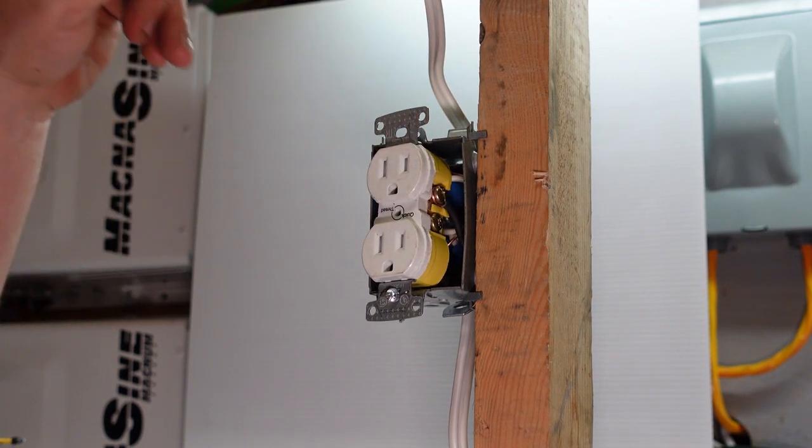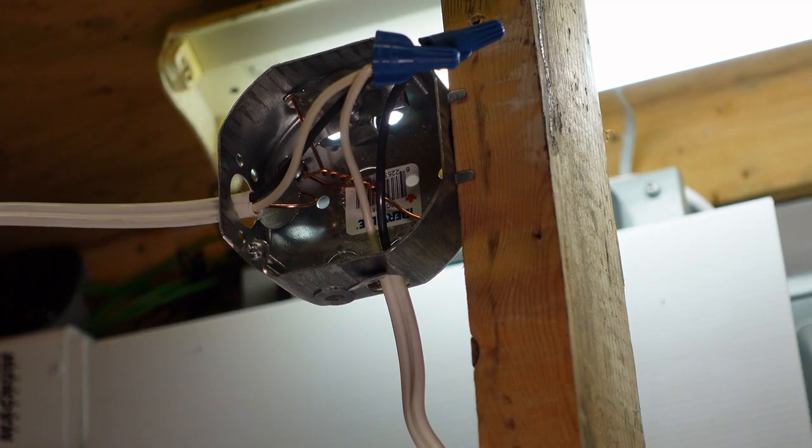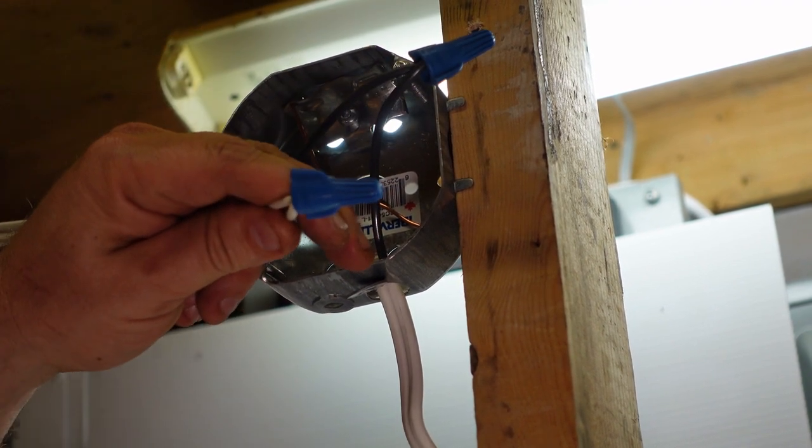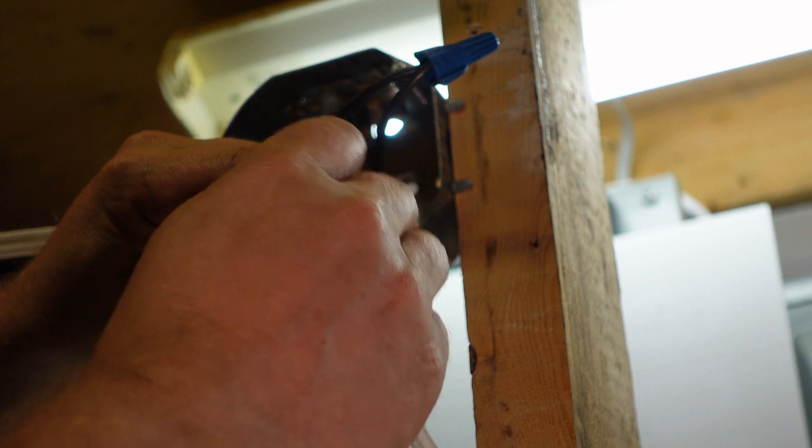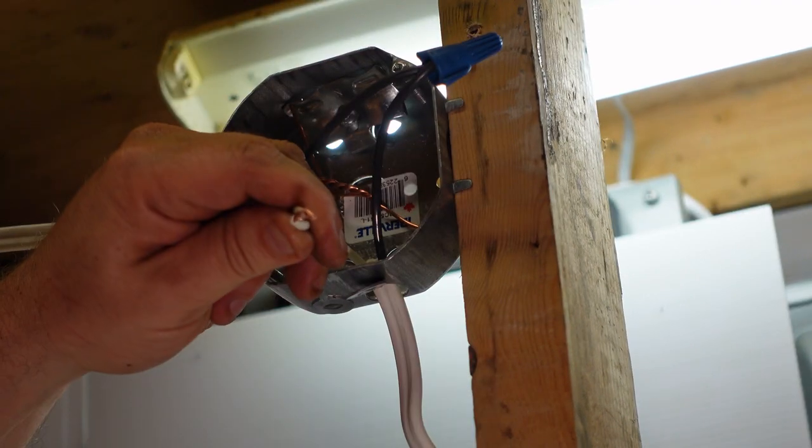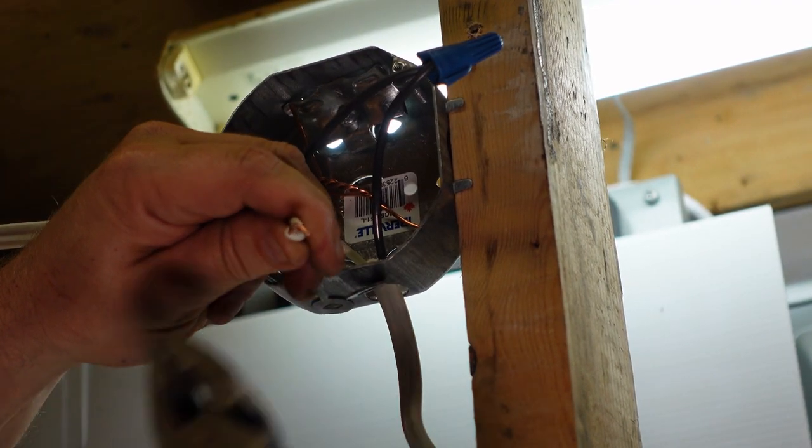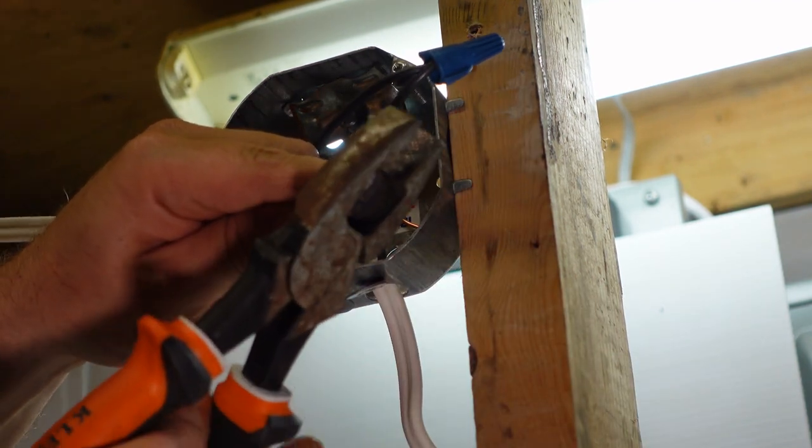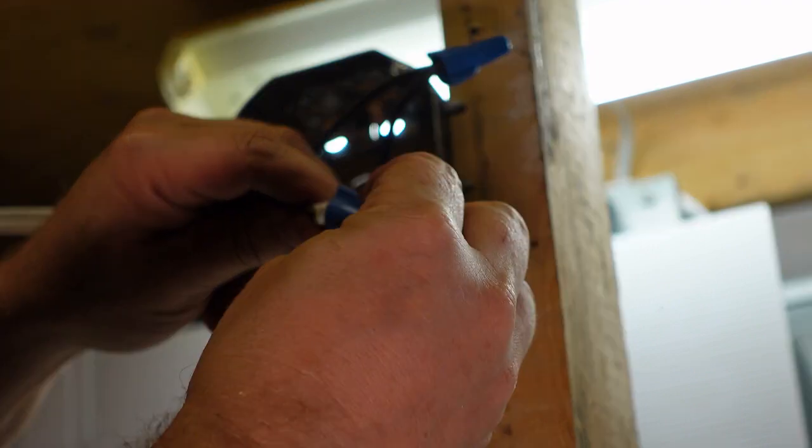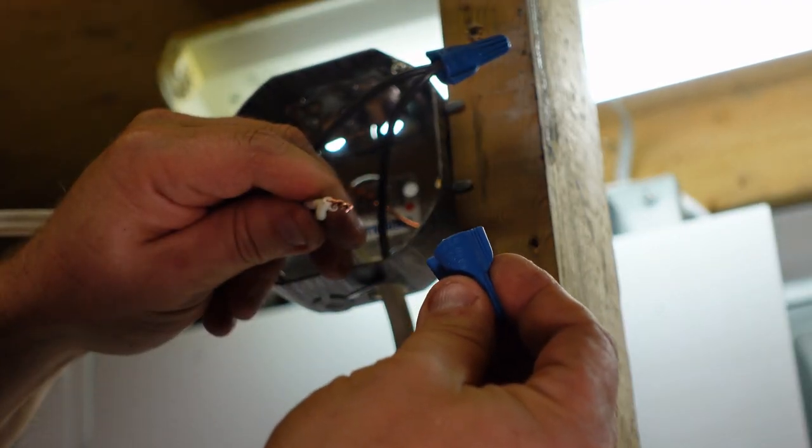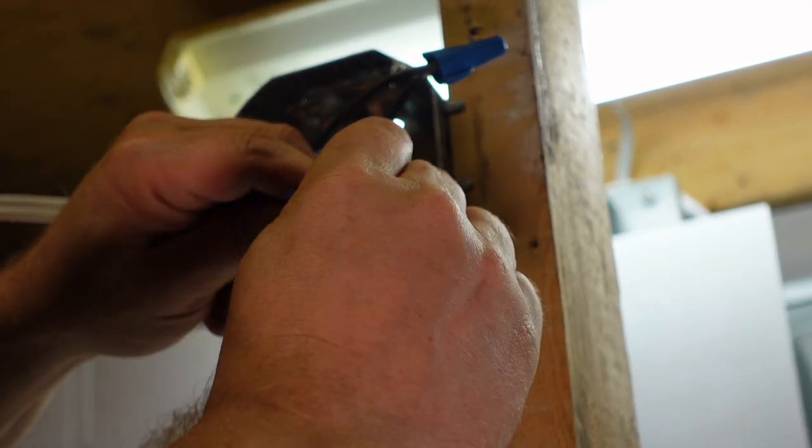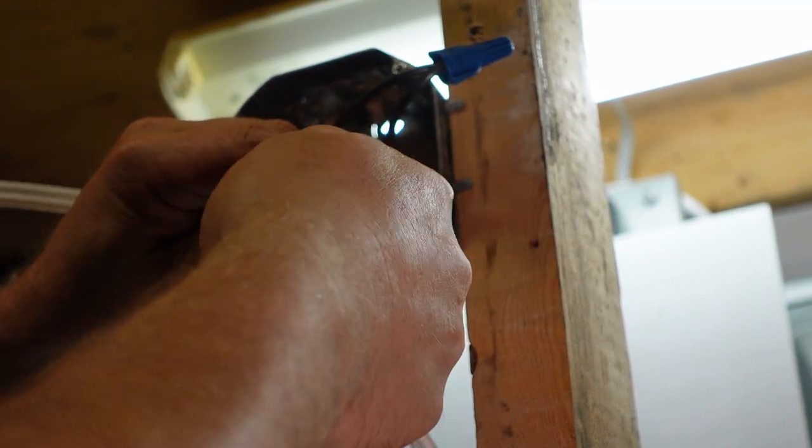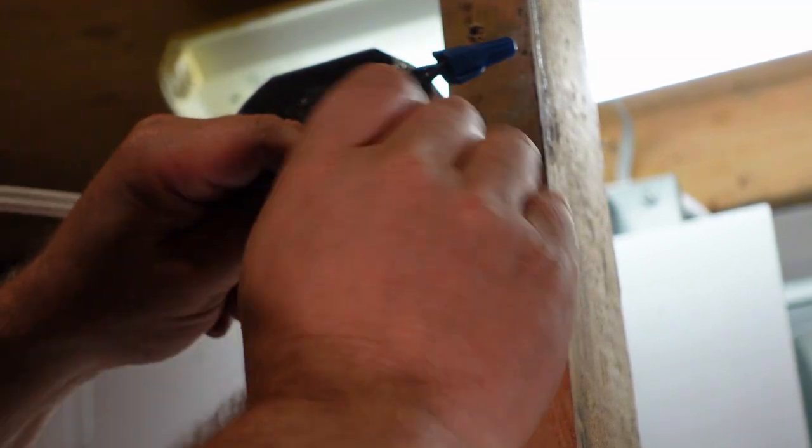Now I'll focus in on the octagon box. The white wire that was too long, we're simply going to remove the marrette, give a couple extra twists, cut the wire shorter on an angle, which helps make the marrette bite better, and then we're gonna put the marrette back on so that we don't see any bare conductors showing.